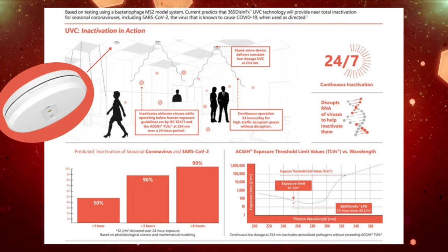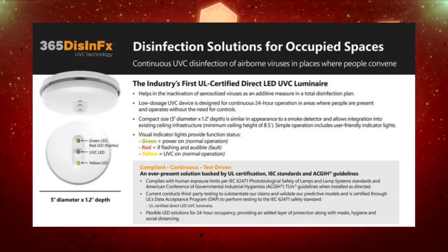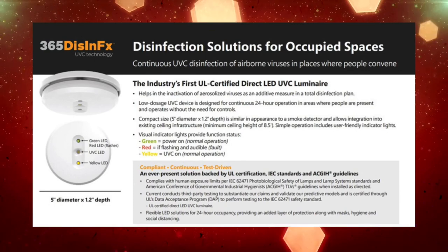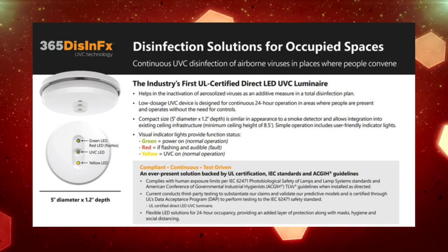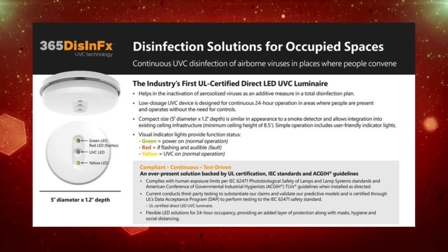The LPU's compact size is a 5-inch diameter and 1.2-inch depth. It is similar to the appearance of a smoke detector and allows integration into existing ceiling infrastructures at a minimum ceiling height of 8.5 feet.